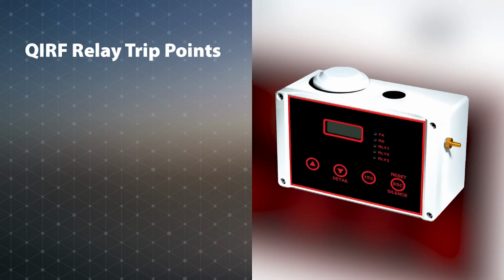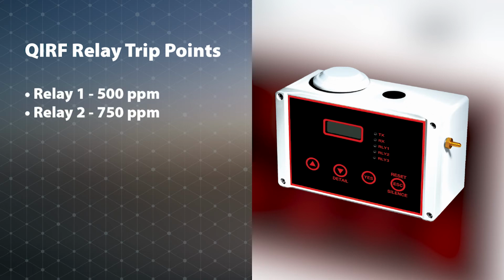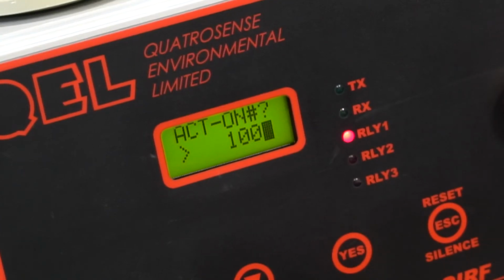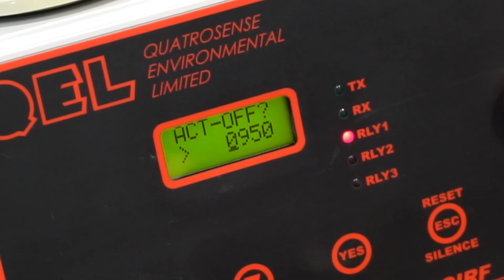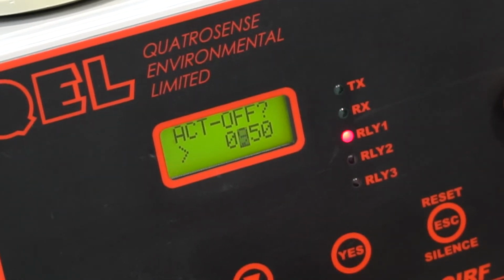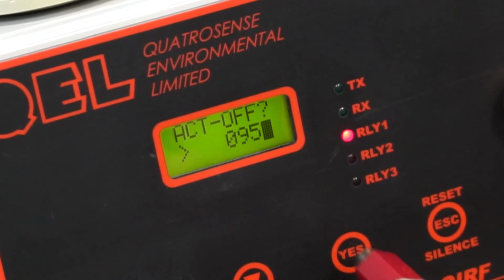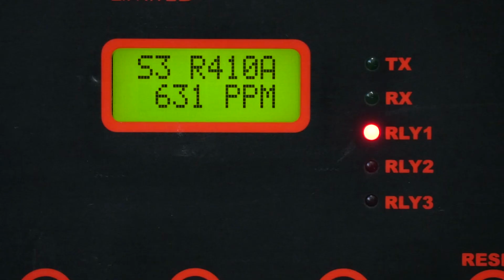The QIRF is shipped with its 3 relay trip points set to the following factory defaults. Relay 1 is set to 500 ppm. Relay 2 is set to 750 ppm. And Relay 3 is set to 1000 ppm. Each relay can be individually programmed to different levels based on local code or sequence of operation using the unit's magnetic keypad.